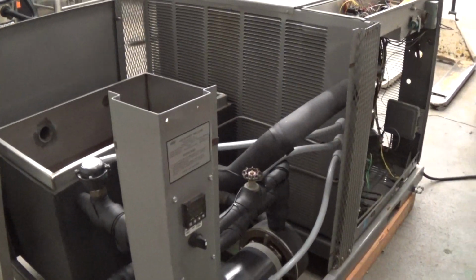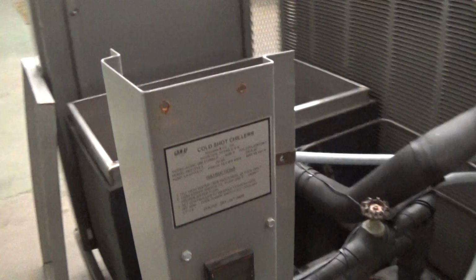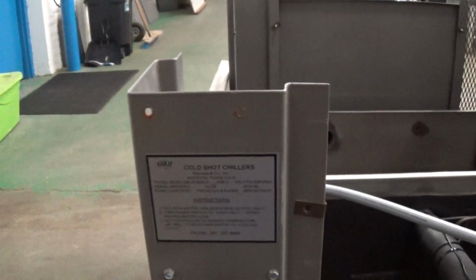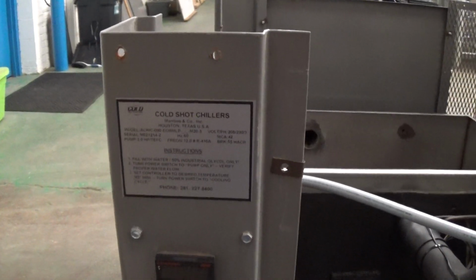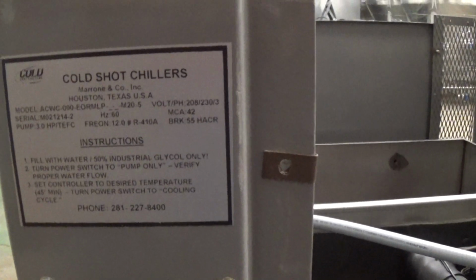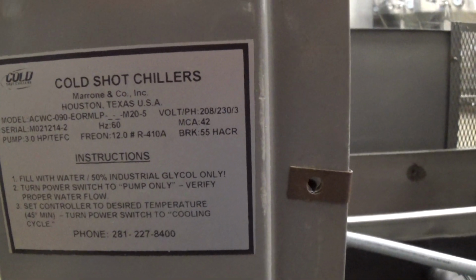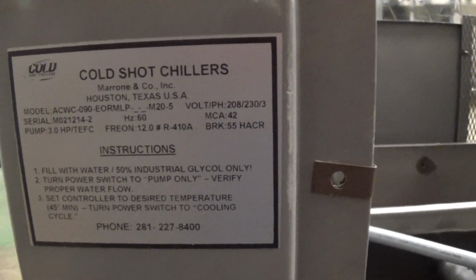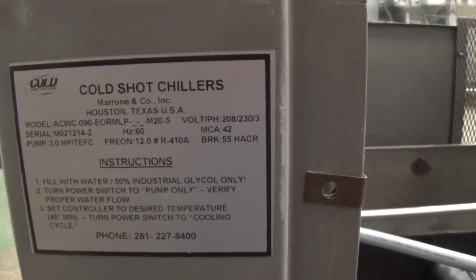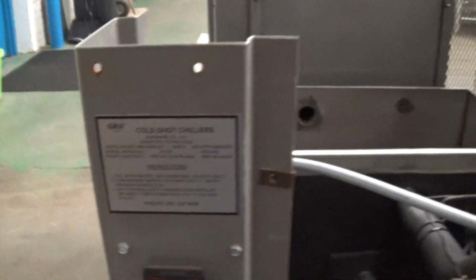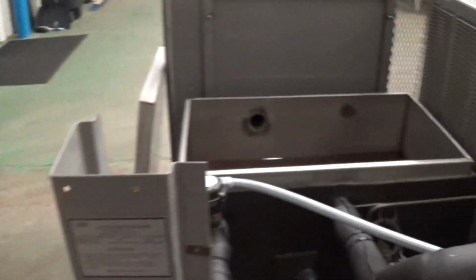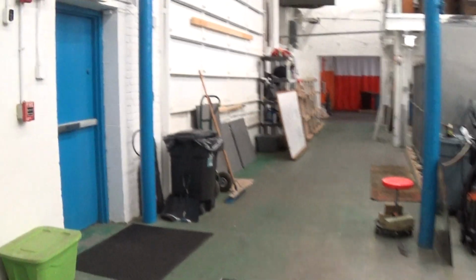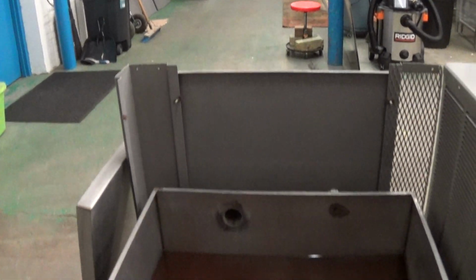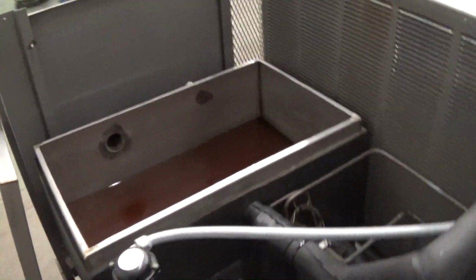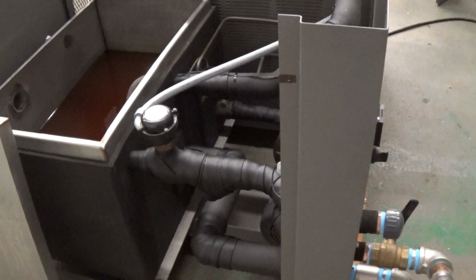We can call it a glycol chiller because we have this set up, tested, and ready for a brewery application. So it's going to chill down to 25 Fahrenheit glycol. This is a 208/230 3-phase machine. Again, 2014, using our 410A refrigerant. And I have the covers off. We have all the covers over there, as you can see, and I have the lid of the tank off also. Just to go over a couple things, some key components and so forth.